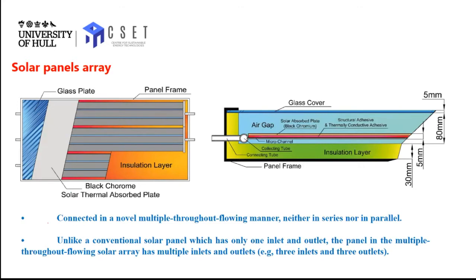We have fluid pass across the low part of the channel, then flow into the second panel, then the third panel, finally to the end panel of the array. Afterward, we have fluid flow backward from the upside channel, then going upward, and the fluid flows forward from the beginning to the end.